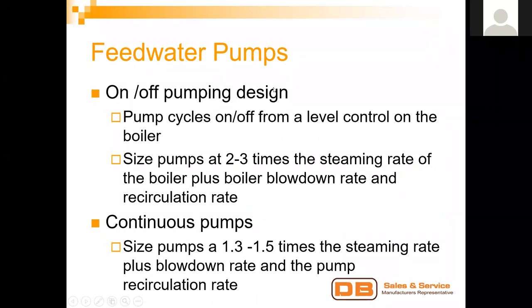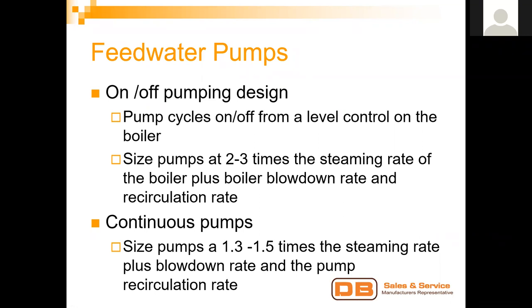Feed water pumps: for on-off pumping, we size pumps at two to three times the steaming rate of the boiler. We take the boiler's steaming rate, convert to pounds per hour of steam, divide by 500 to get GPM, then multiply by two to three times to ensure the pump has more than enough water each time the boiler kicks the pump on. For continuous pumps, we divide the steaming rate by 500 for GPM, then multiply by 1.3 to 1.5 times the steaming rate, plus blow down rate and pump recirculation to avoid deadheading.